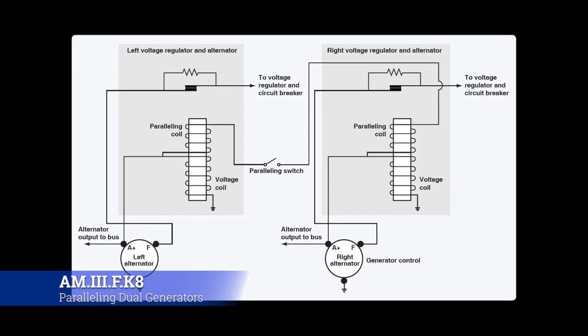This is where your bus tie breakers and all this stuff start to really factor in. The initial setup has one generator typically online supplying the load, whereas the second generator kicks on, is started, and brought to the same voltage, frequency, and phase as the other. Once they've synchronized, they then start balancing the load off each other.